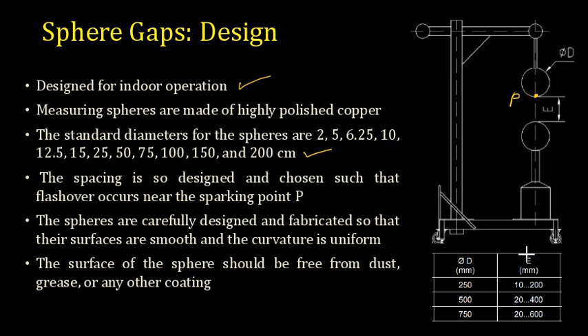Now for different diameters, different spacings are provided. For this particular design, if you have a diameter of 250 millimeter or 25 centimeter, we can have a spark gap between them from 10 millimeter up to 20 centimeter. So you are able to adjust it like that. You are given the option of adjusting the distance between them for a particular diameter of the sphere. Once you change the diameter, you are able to adjust the gap distance from 20 millimeter up to 60 centimeter. Such adjustments can be made in the experiment setup.